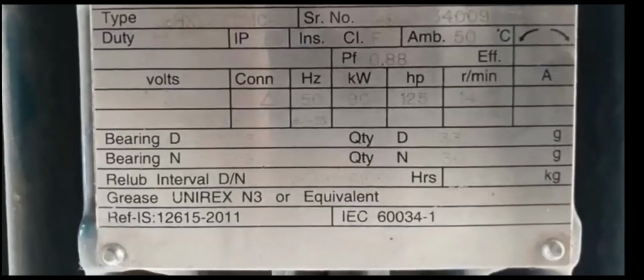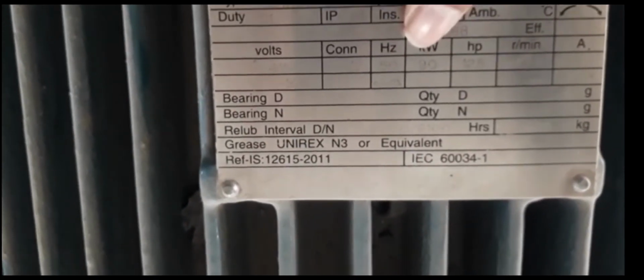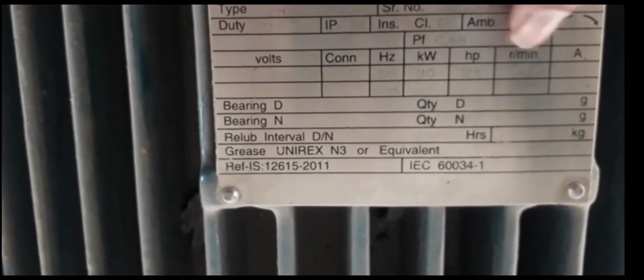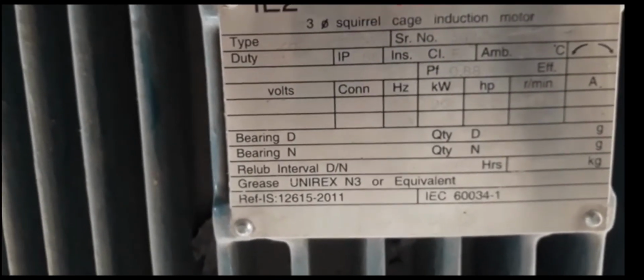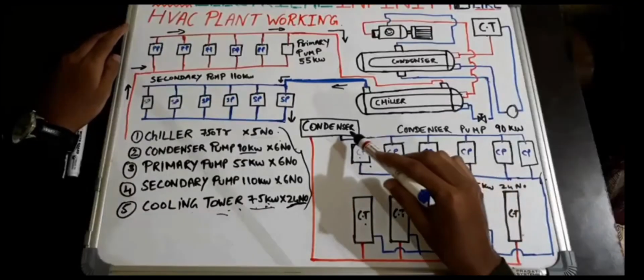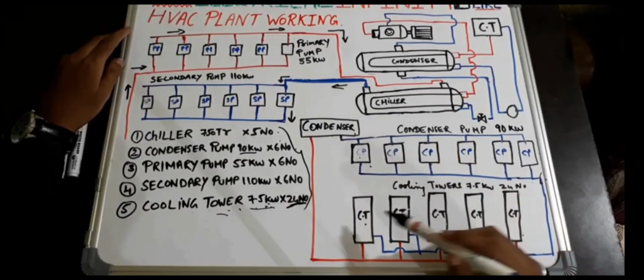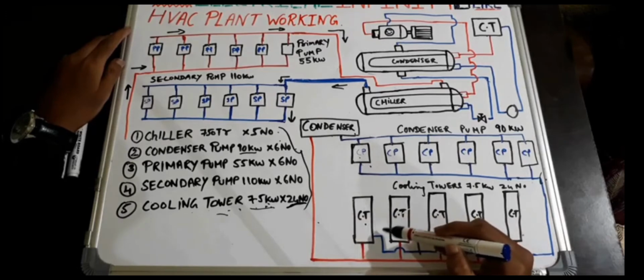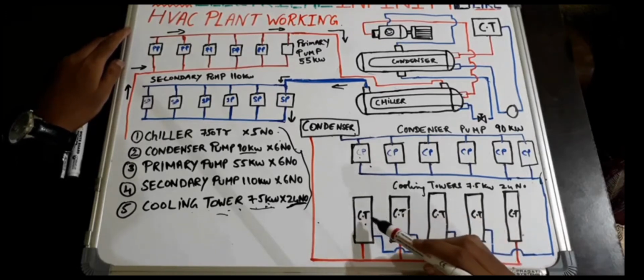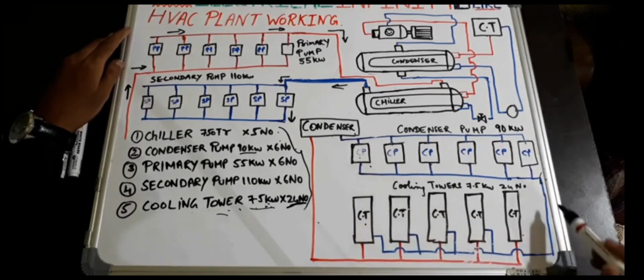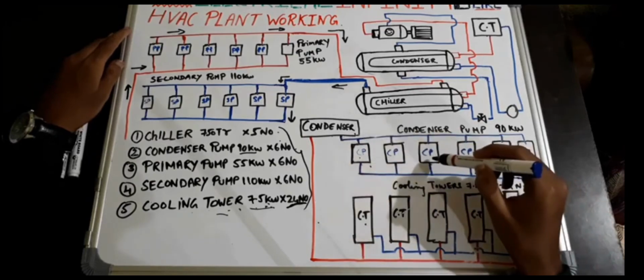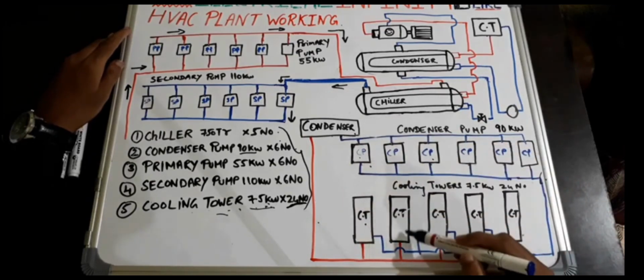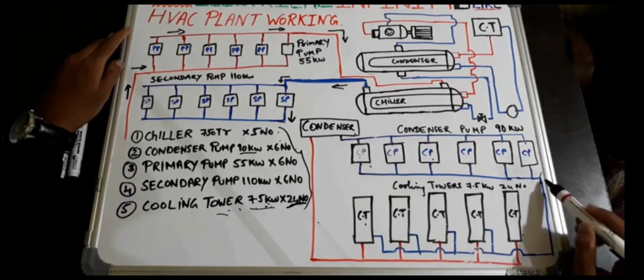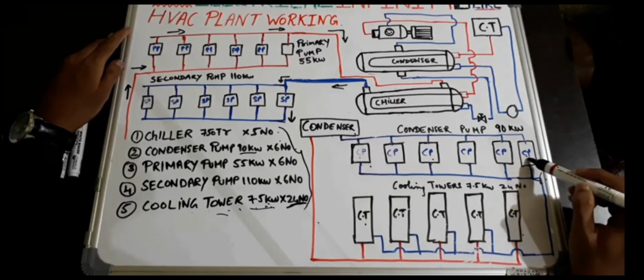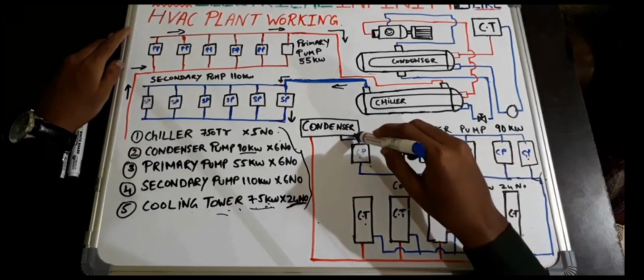These are the details of the motor plate. As you can see here, this is a 90 kilowatt, 125 HP, 50 Hz motor. Before proceeding further, let's learn about the working of this part only. Here you can see we have the condenser pump and a cooling tower. Red line means hot water and blue line means cool water. As you can see here, the cool water from the cooling tower is pumped into the condenser with the help of the condenser pump. Here you can see the cool water from all these cooling towers enters this condenser pump and this water is pumped to the condenser, as you can see here.